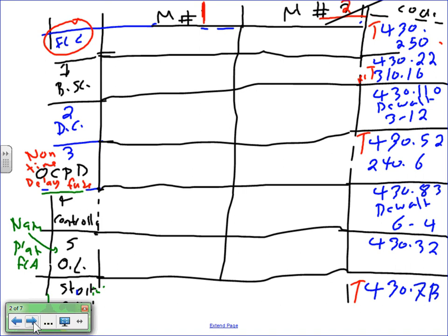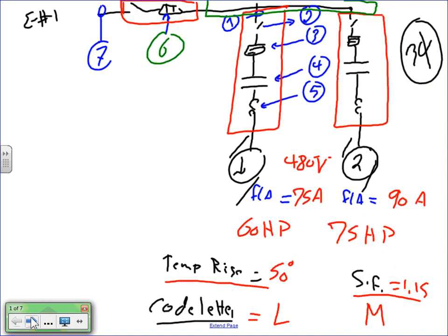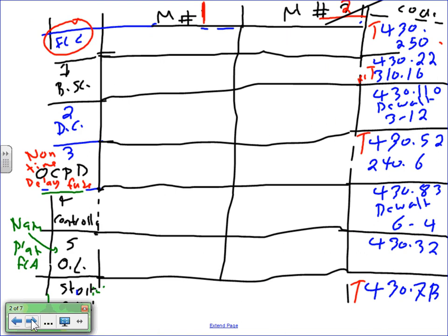So you're going to go to Table 430.250. We went there many times and find the full load current for these motors. What type of motors do we have, guys? We do have 60 and 75 horsepower motors. They're both at 480. So when you go to the table, you're not going to find 480. You're going to find 460. Why? Because they rate them at a slightly lower voltage, so they can handle it if you have a low voltage in your line. They're not going to be grossly affected by it. Okay, so if you guys go there, please correct me if I'm wrong here. This should be 77 amps, and this baby should be 96 amps.